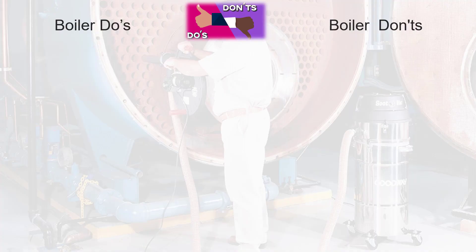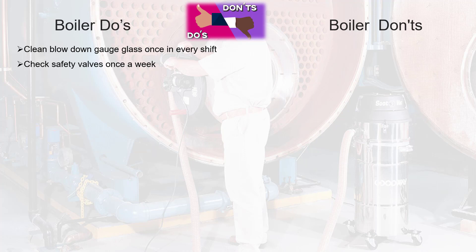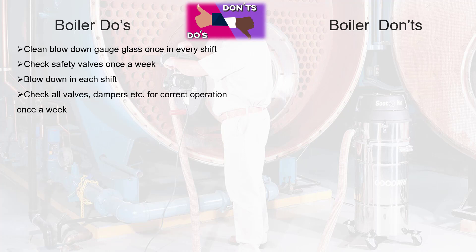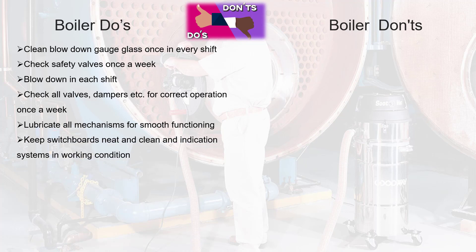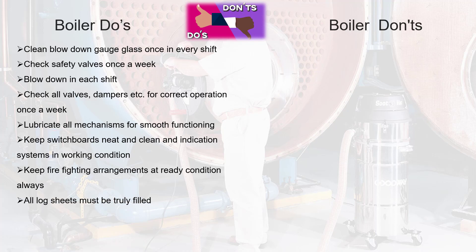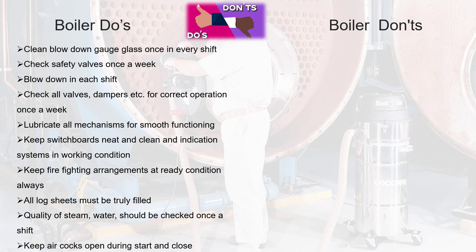Boiler DOs: clean blowdown gauge glass once every shift. Check safety valves once a week. Blowdown each shift. Check all valves, dampers, etc. for correct operation once a week. Lubricate all mechanisms for smooth functioning. Keep switchboards neat and clean and indication systems in working condition. Keep fire fighting arrangements at ready condition always. All log sheets must be truly filled. The quality of steam and water should be checked once a shift. Keep air cocks open during start and close.